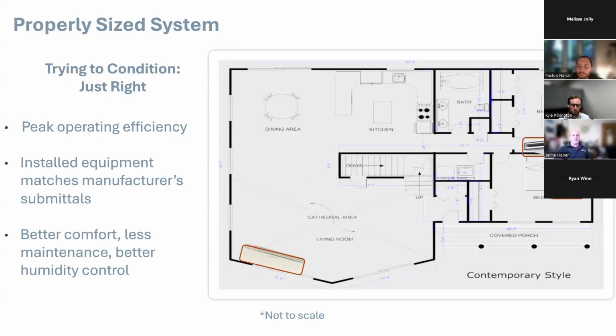So it's really important to get a properly sized system. We'll talk about something called Manual J, which is the sizing calculation — a very amazing, holistic approach to sizing a heat pump, way better than what they used to do, which was stand at the curb, hold up a few fingers, and figure out it's this big. No, we don't do that anymore. When it's just right, you get peak operating efficiency, and it really works the way it's designed to work from the manufacturer.